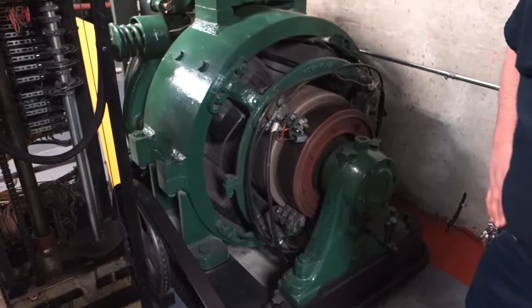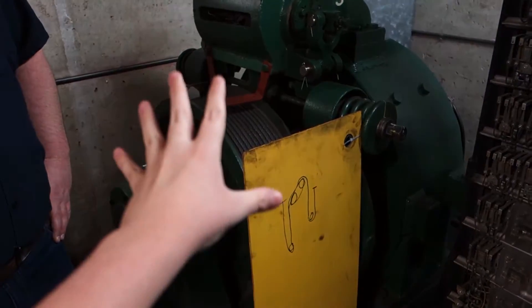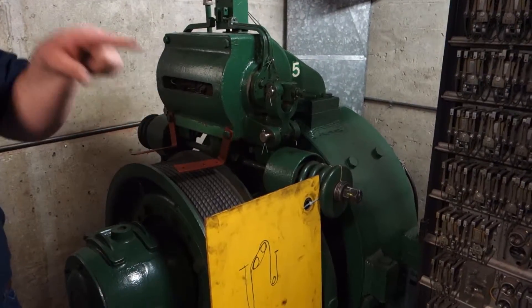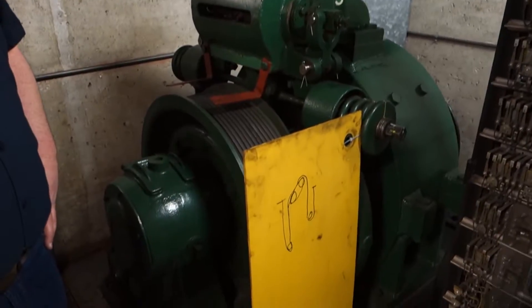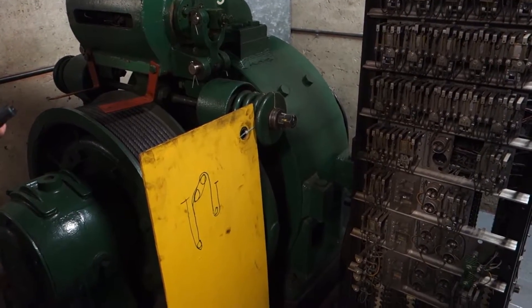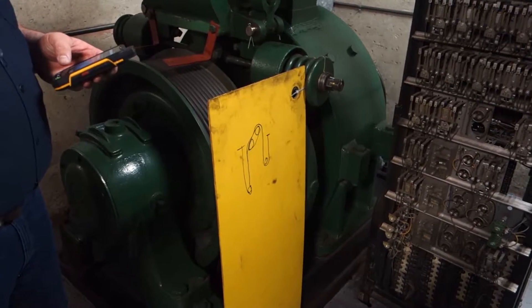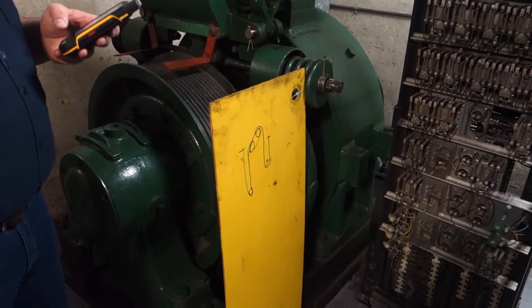There's that one going — this is so cool. They should keep the machines. What's being upgraded — the motors, or just the electronics? Usually it's the relay cabinets — all the controls will be computer boards now. They'll probably keep the DC motors but use DC drives. They don't build like that anymore — they're great motors. A machine shop can come in, redo all the windings, re-insulate them, and they're good to go. If possible, I'd like to get some of the old call stations and buttons from the floors when they take stuff out — I collect elevator buttons.